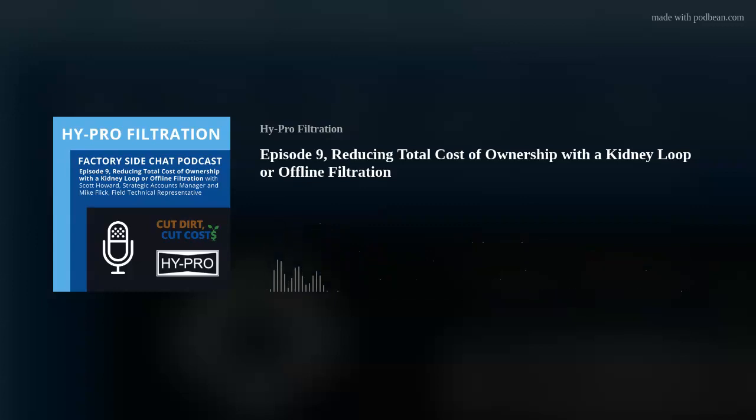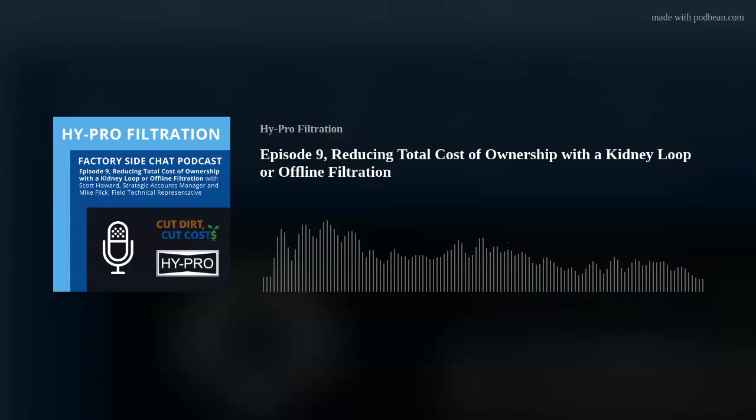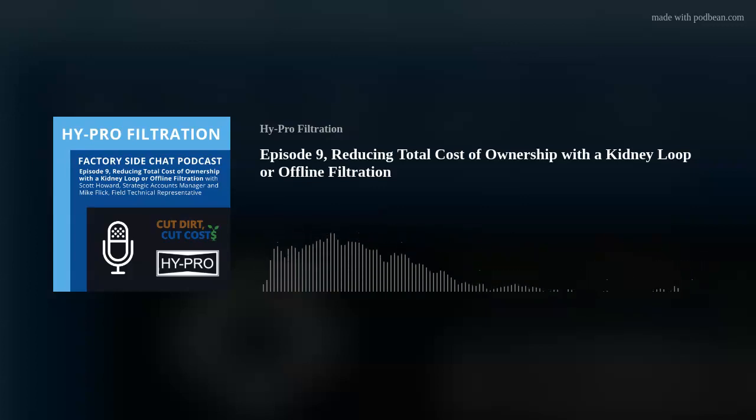Where if we can change the filters on scheduled downtimes when we know, for example, let's say we know the filter is going to last 4 months approximately. That means when we're getting into that 4 month range and I have a 90-day shutdown schedule, instead of waiting 4 months, I'll change out those pressure filters and those return filters on the 90-day intervals. So yeah, we may be losing a little bit of filter life by doing it that way, but think about how much production you're going to lose on just 1 hour for shutting down to change out a filter.